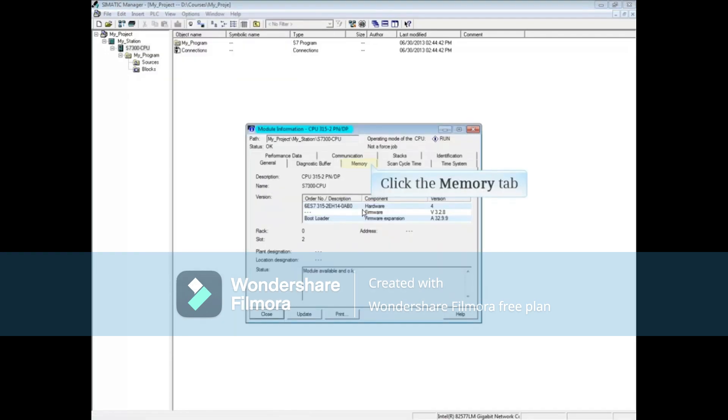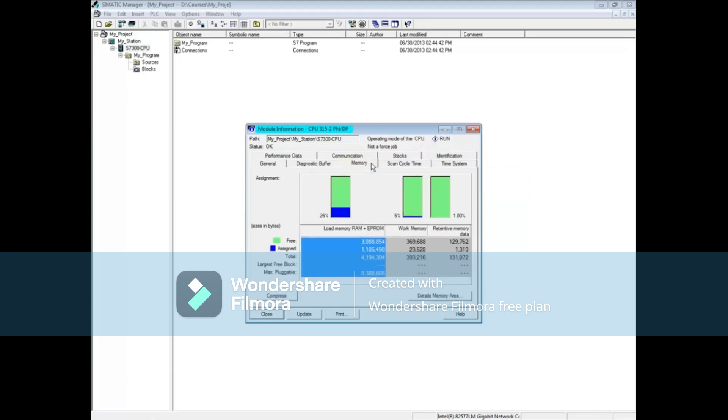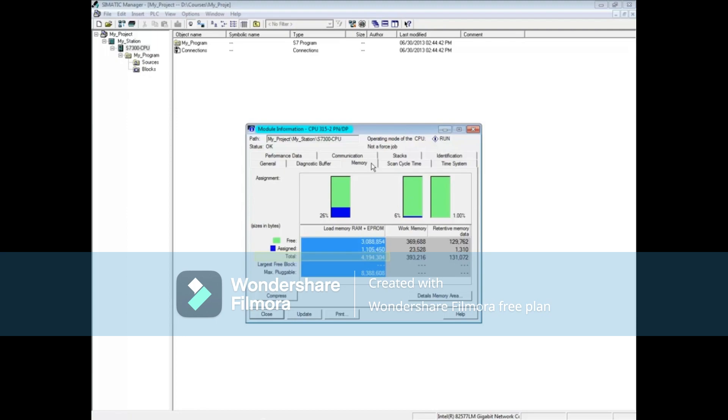Click on the Memory tab. In the case of the S7-300, the CPU's RAM or load memory is the Micro Memory Card or MMC. The max MMC that this CPU can take is 8 megs. The size of the actual MMC is 4 megs.